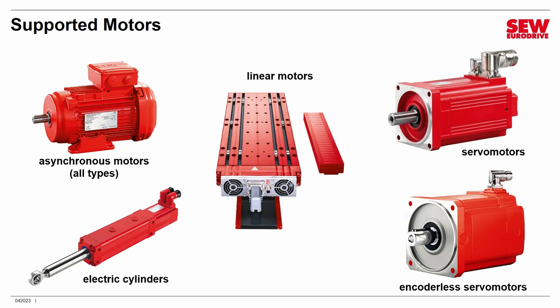There are some limitations — you cannot do positioning with an encoderless servo motor, but you can certainly use it in various kinds of speed and torque control applications. As you can see, we're pretty much covering just about every imaginable motor type in industry with the MOVI-C products. To support all these motors, our VFDs contain four different motor control modes that determine how they manage the motor.